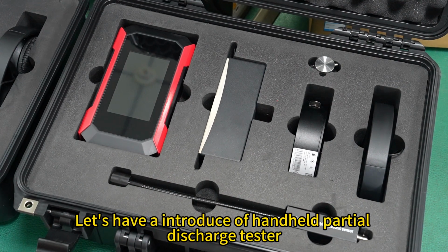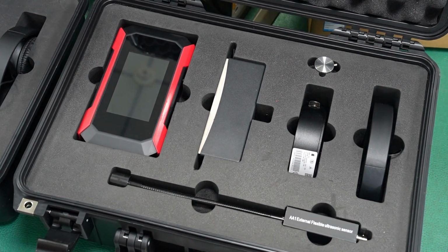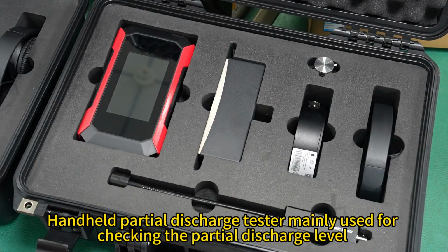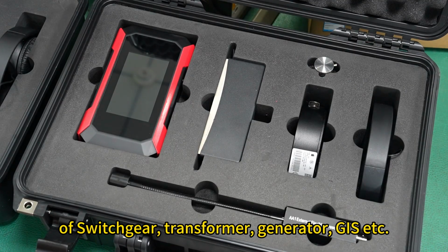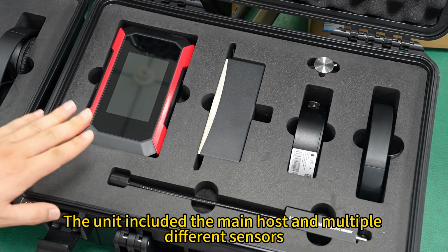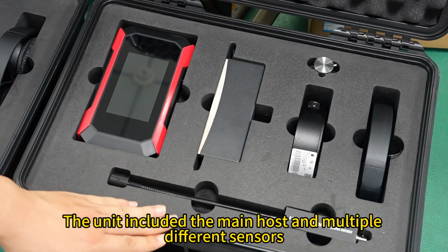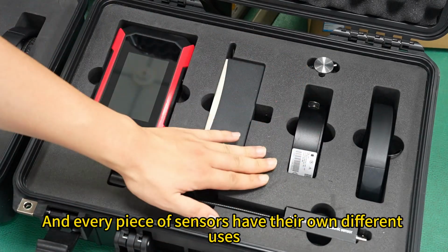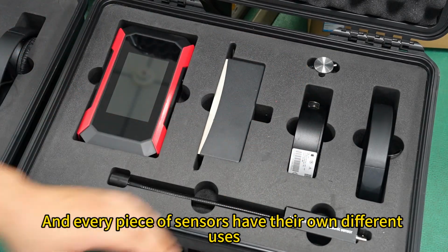Let's have an introduction of the Handheld Partial Discharge Tester. The Handheld Partial Discharge Tester is mainly used for checking the partial discharge level of switchgear, transformers, generators, GIS, etc. The unit includes the main host and multiple different sensors, and every sensor has its own different use.